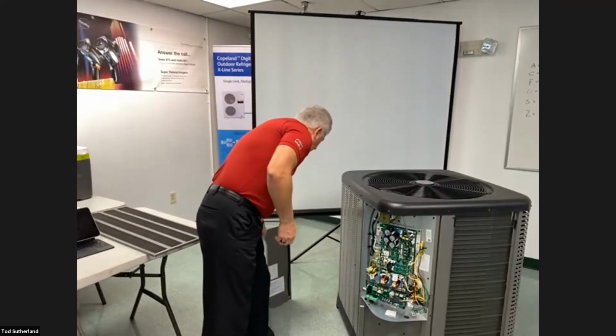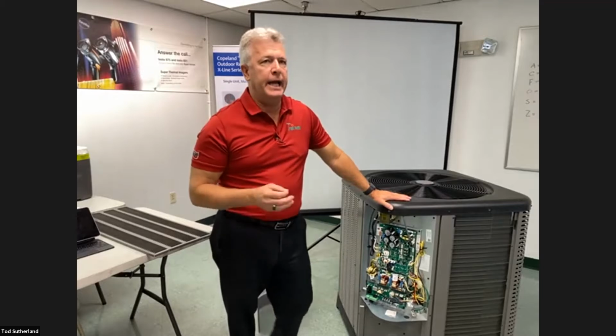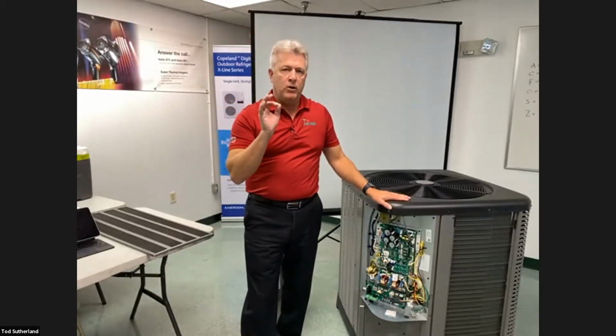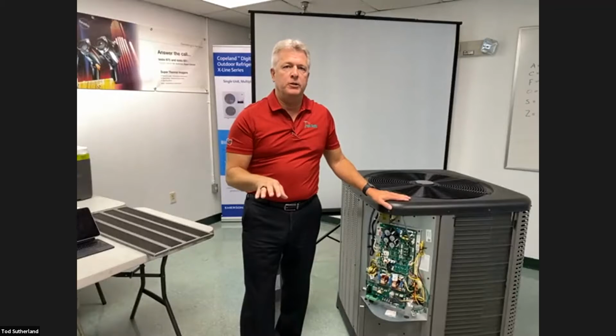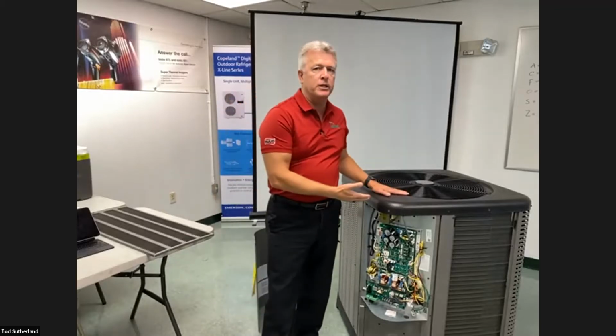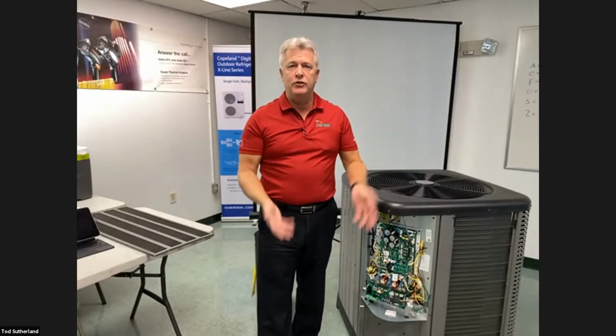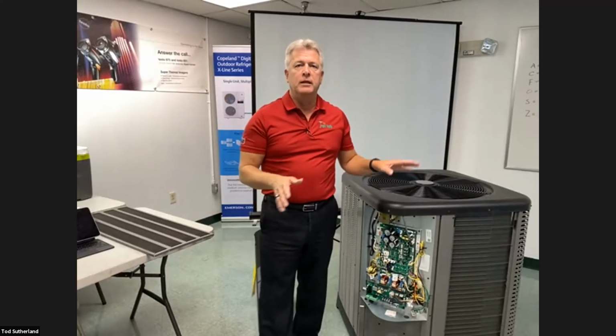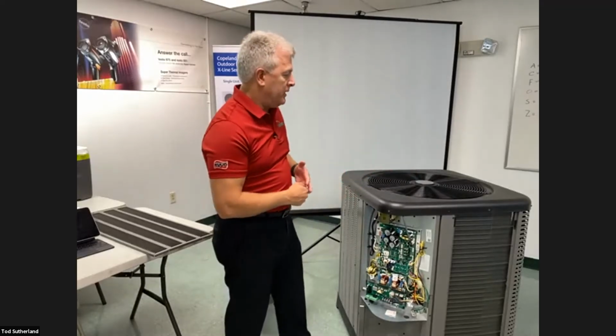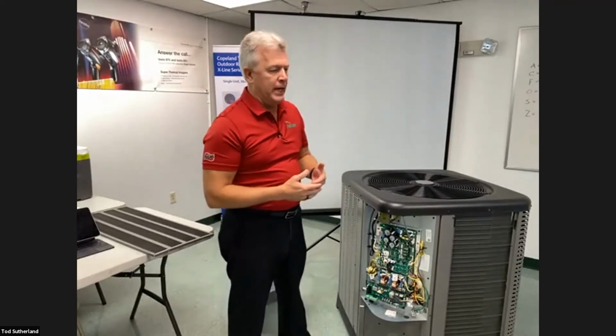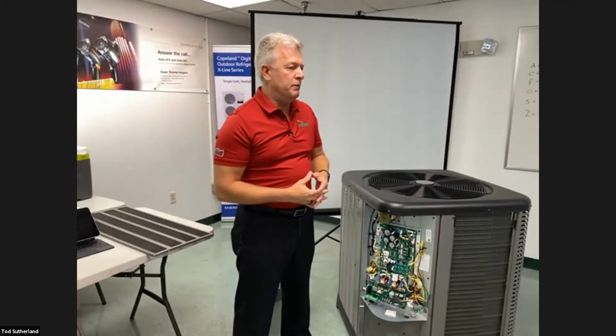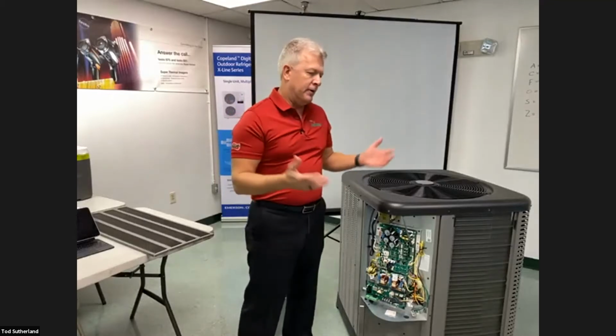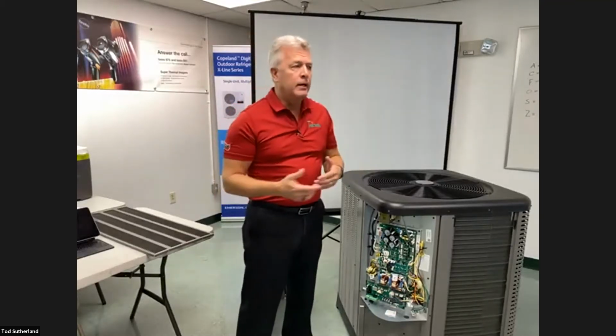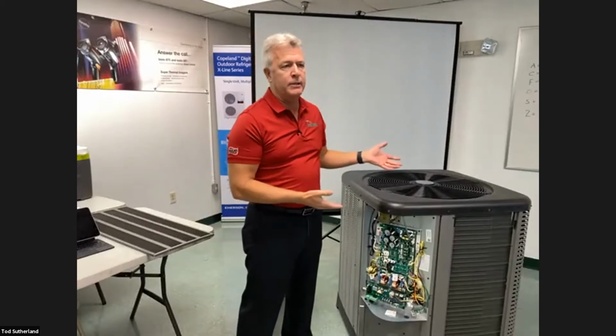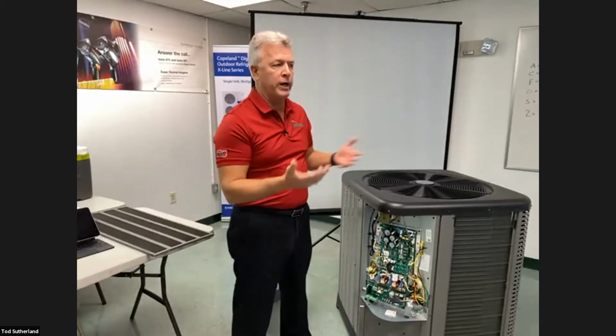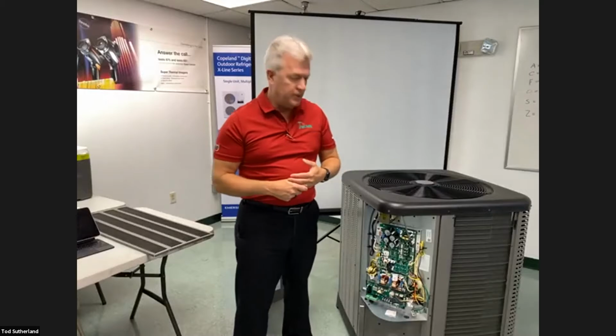Okay. As far as wiring goes on all the inverter systems, you can wire these what we call legacy wiring, but you really don't want to, because when you do, it basically takes the inverter system and turns it into a single stage unit, which is completely defeating the purpose of selling the inverter system. The only time you'd really want to do that is if you have a problem with the Econet controller, maybe an issue with communication, where you would wire it up legacy wiring in an emergency, so you could get the system running until you can figure out what your other issue is. Okay.